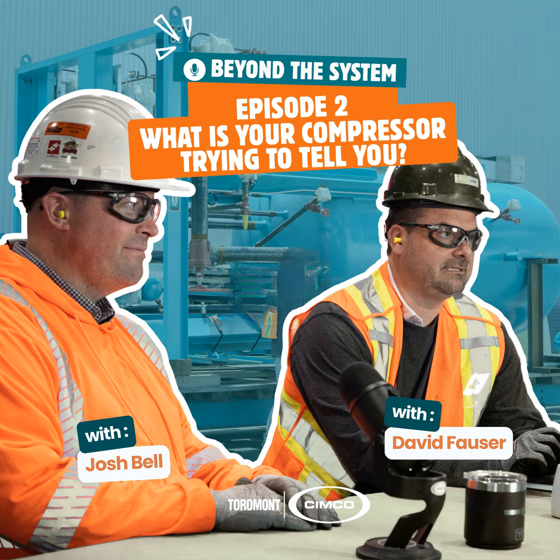And so, keeping an eye on those things, obviously cleanliness around the machine will help you identify these things. If you have a very disorganized, dirty room, oil might be accumulating on the floor or maybe under a box that you haven't moved, and you won't notice it until it gets worse. So pay attention to oil leaks, monitor all your pressures and temperatures. And then also your belts or your couplings. If it's a direct drive, often there'll be a metal coupling.